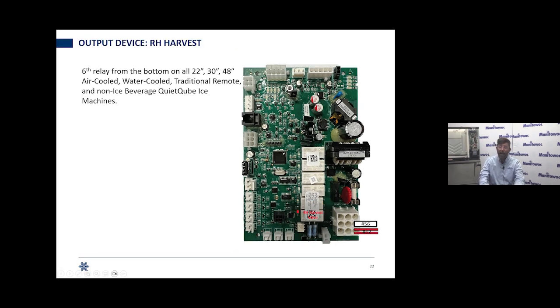All right, and then the right-hand harvest valve. The last relay on the bottom, this is only utilized on dual evaporator machines, not dual circuit, single plate, two evaporators side by side. So again, that IF 14, 18, and 2100, this will come on every time that the left-hand harvest valve comes on on machines with multiple evaporators. And you can check across 62, which is a red and white striped wire, and 56, the white wire.